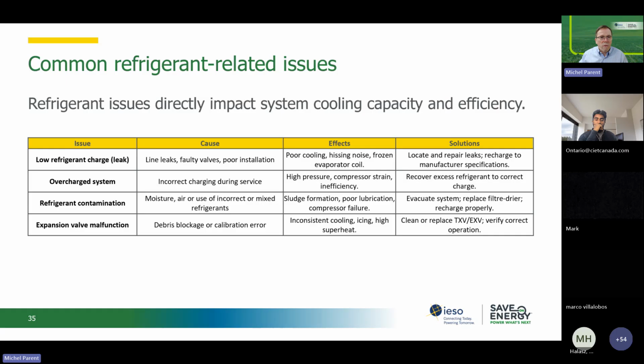When you have low refrigerant charge, you will have a very easily frozen evaporator coil when it's a DX system, and you will lose a lot of capacity. As you lose refrigerant, your system will lose capacity, so you can no longer provide enough cooling. Eventually, to try to compensate, it keeps getting the evaporating pressure lower and lower, which creates freeze-ups. And you'll see a lot of freeze-ups on your lines and on your evaporator.